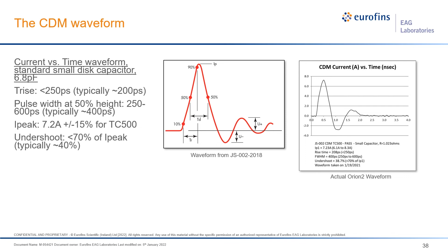Typically, it's 400 picoseconds. For reference, remember the old JEDEC C101 waveform? Part of the reason the JEDEC spec had a problem was the pulse width at half height had to be 500 picoseconds to 1500 picoseconds wide. This simply isn't realistic. For the JS-002 test head, the peak is supposed to be 7.2 amps, plus or minus 15% for test condition 500, when measured with a 6 gigahertz or higher oscilloscope, which is what the 500 volt condition is now called, with an undershoot of less than 70% of iPeak.